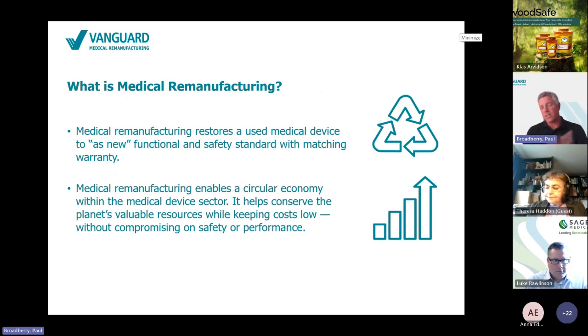Essentially, we take some previously deemed single-use medical devices that you ordinarily throw away and turn them back into a new single-use device. Let's take a harmonic scalpel as an example, which is used in laparoscopy cases. The original is made in Mexico using valuable earthly resources. It's shipped through the supply chain to a hospital near you where it's used for a few minutes at a time and then thrown away. These devices are expensive and complicated. So all we're saying as a remanufacturer is please don't throw it away, give it to us.